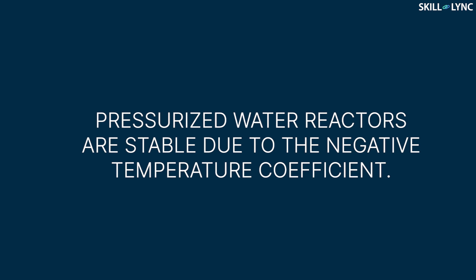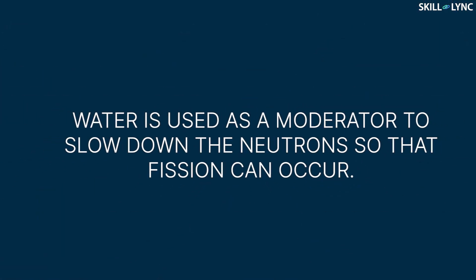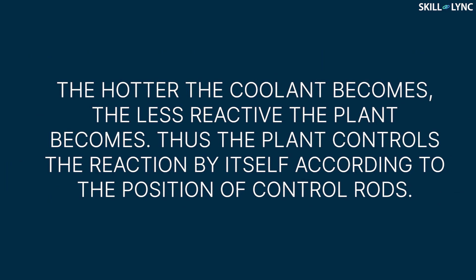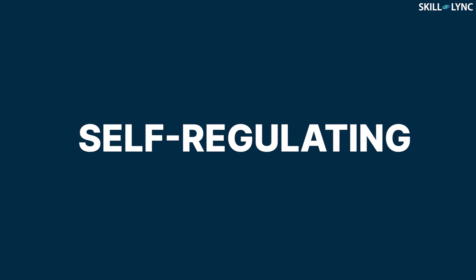One interesting property that makes pressurized water reactors very stable is the negative temperature coefficient. Water is used as a moderator in pressurized water reactors because water molecules slow down the neutrons to facilitate nuclear fission. But when the temperature of water increases, it expands, making it less dense. So, the probability of slowing down the neutrons decreases, which reduces the rate of reaction. Therefore, if the rate of reaction increases beyond normal, the moderation of neutrons will be reduced due to the expansion of water and the chain reaction will slow down. This property is called the negative temperature coefficient and the process is referred to as self-regulating.